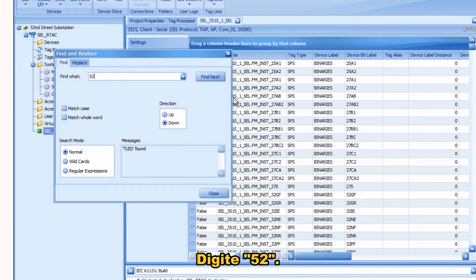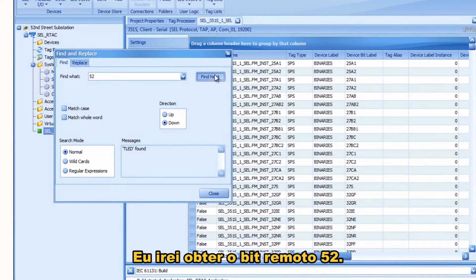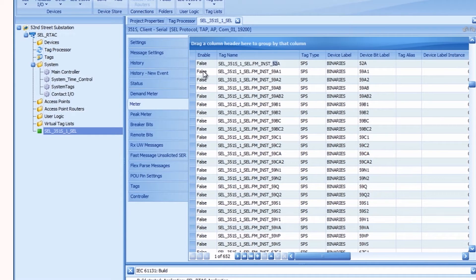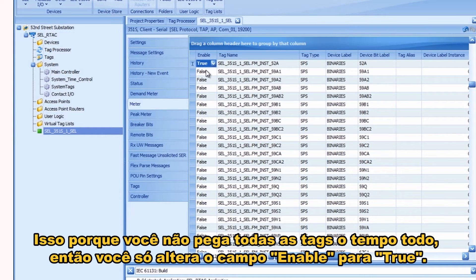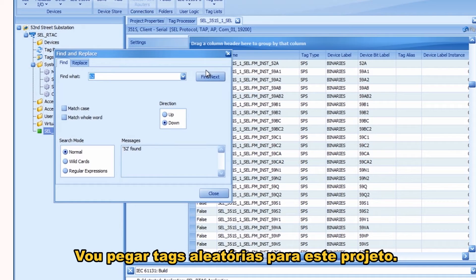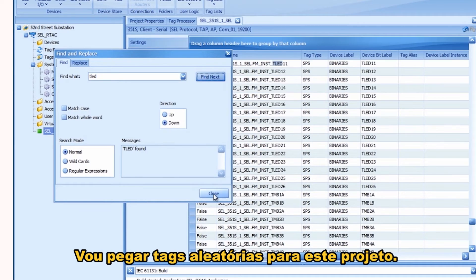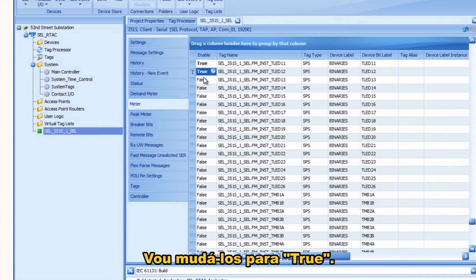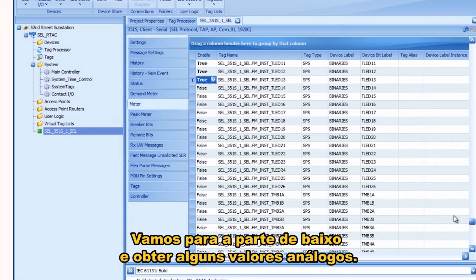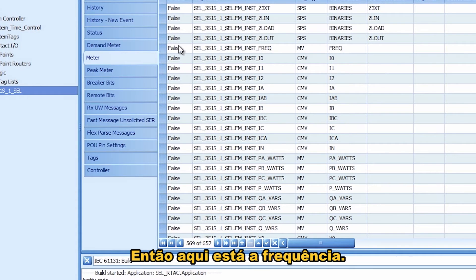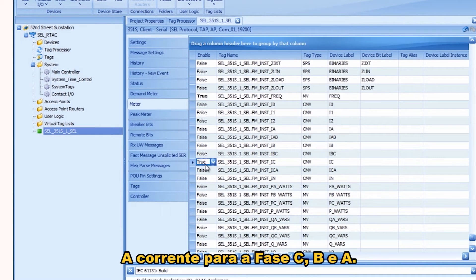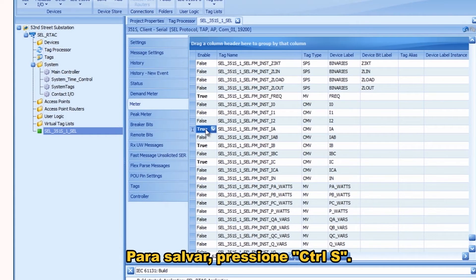I'm going to select some bits and some analog values to bring back from that meter. I'll do Ctrl+F for Find, type in '52', and get the 52 remote bit. Just double-click on 'false' to change it to 'true'. You'll notice all of them are disabled by default — that's because you don't want to pull all tags all the time. Let's grab some more: some TLEDs, change those to true, then go to the bottom and get some analog values — frequency, and current for phases C, B, and A.